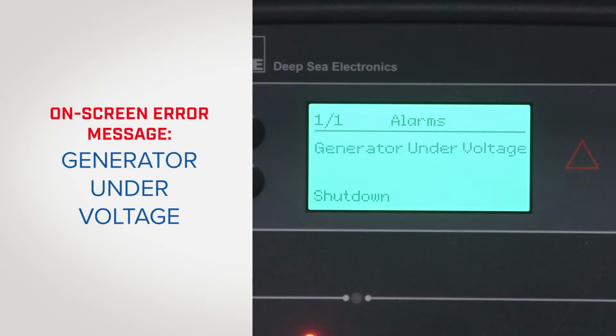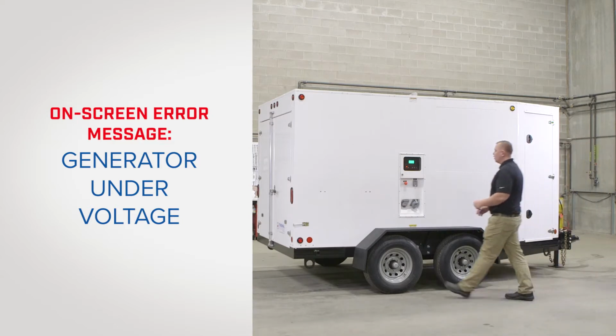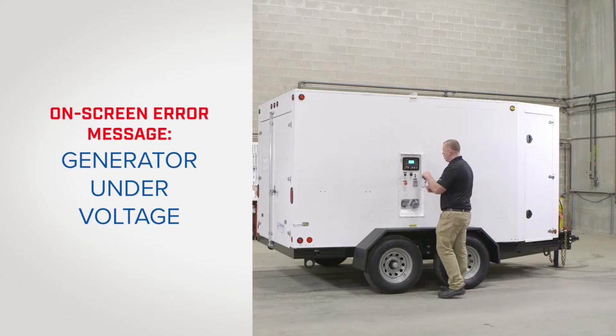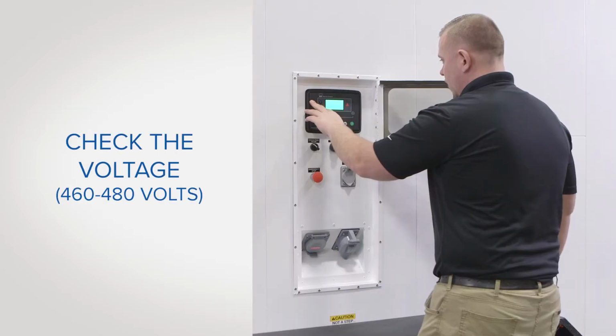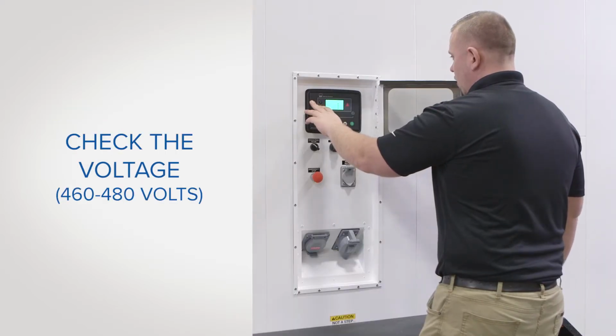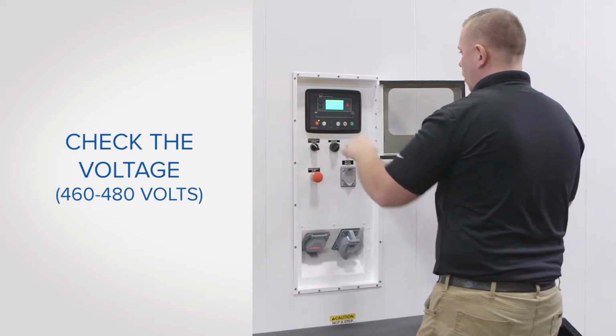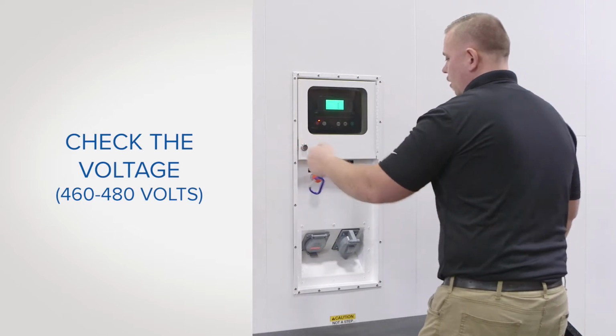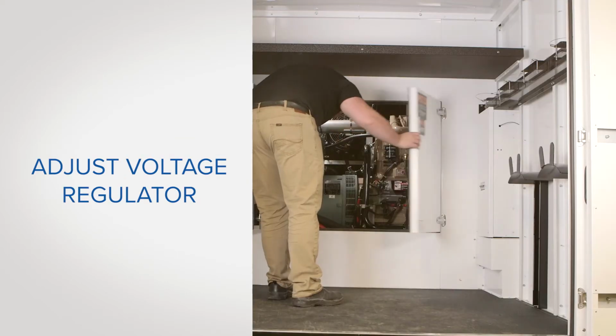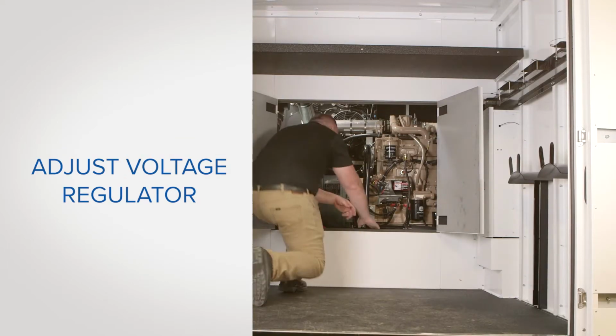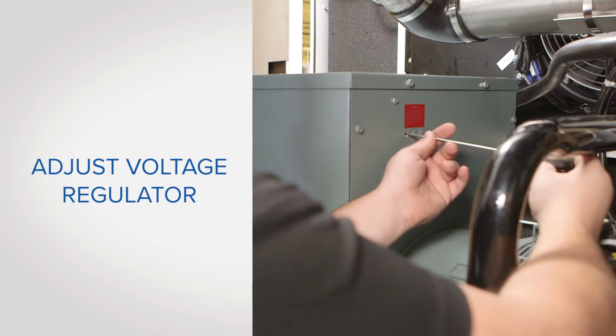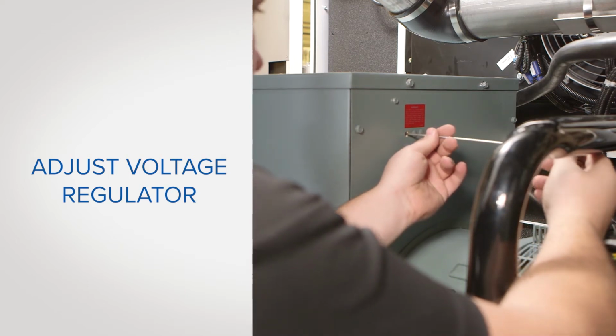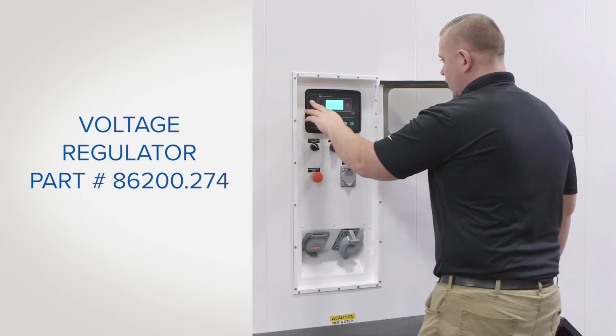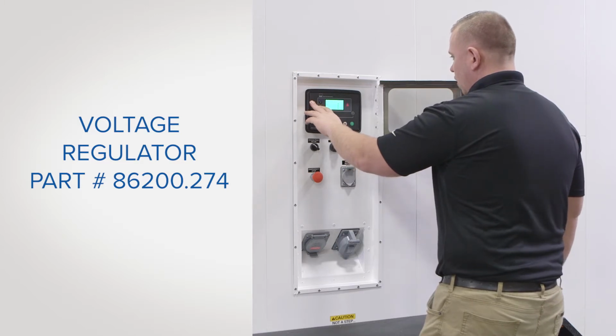You may see a generator under voltage warning on the control panel screen. To determine that your generator is operating at the proper voltage, check the controller for the voltage reading. The reading should be between 460 and 480 volts. If you are not getting that reading, you likely have a bad voltage regulator or the voltage regulator needs adjusting. After adjusting the regulator, recheck your readings. If not resolved, you need to replace the voltage regulator.